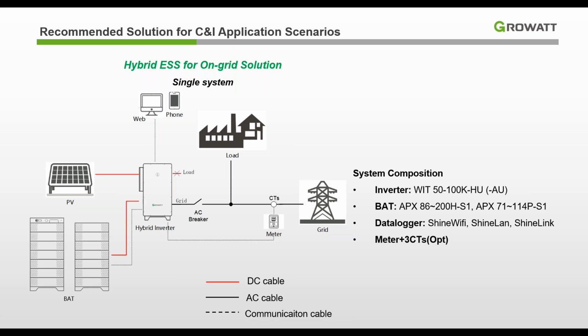Then here you just connect your AC on your grid port, and here's the AC breaker, which is for the AC. Connect to your grid, and now you can just connect here. This should be the distribution board. Then you can connect your loads to the distribution board, which would be on the same level.